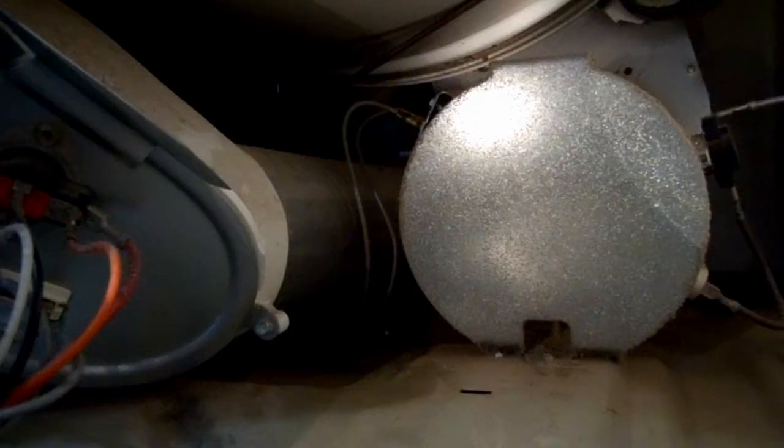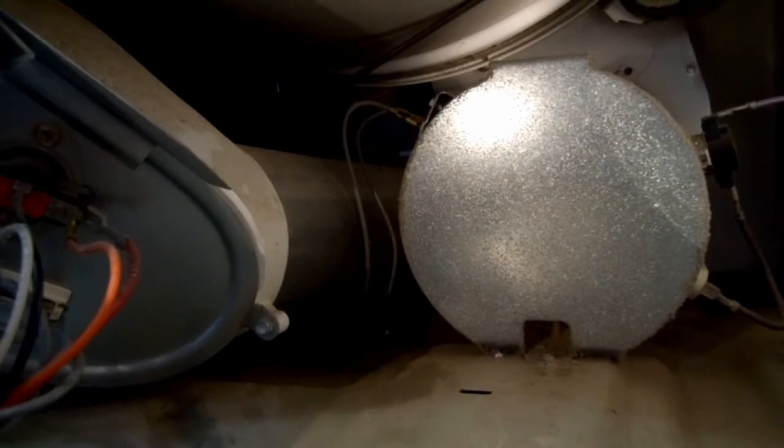And this was the reason, what's known as a burn off. Due to a bad connection and the high temperature caused by electricity under stress, the live wire that ran into the heating element got red hot, softened, and slipped out of the crimp on connector due to vibration.